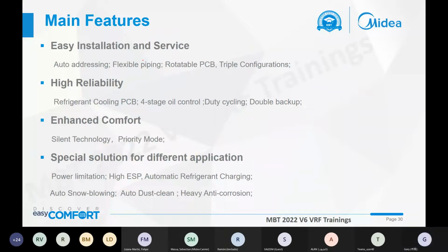Okay, let's go through this part one by one. The first one is auto addressing. For VRF systems, normally we have many indoor units in one system, so we should give each indoor unit an address. In the older generations, we had to set each indoor unit one by one. It really wasted time and was a lot of work. But for the V6, we have auto addressing. You just select this function in the outdoor unit. You don't need to set any address in the indoor unit.